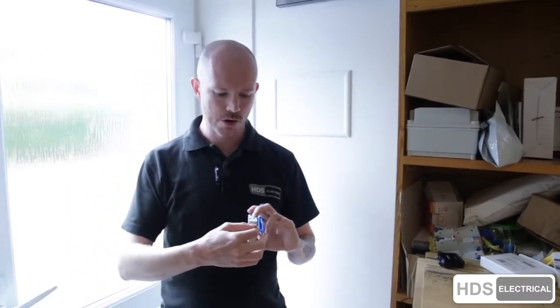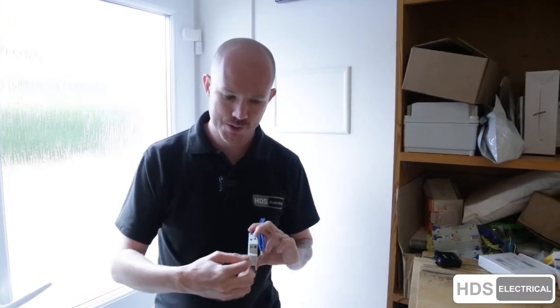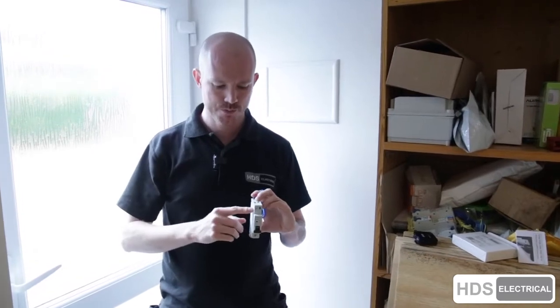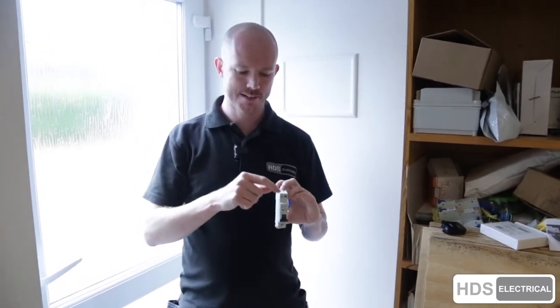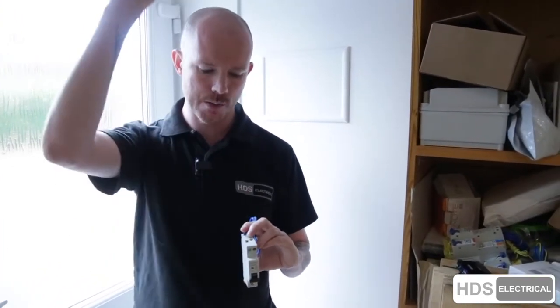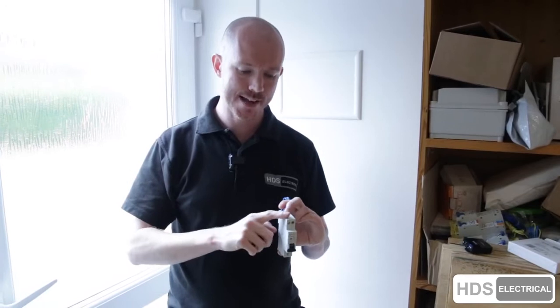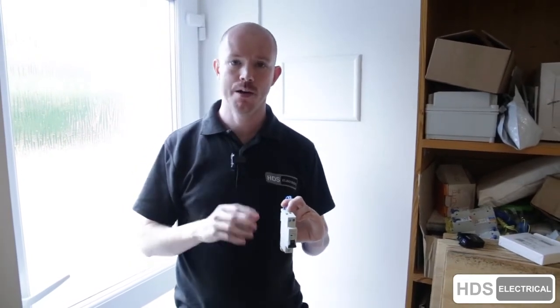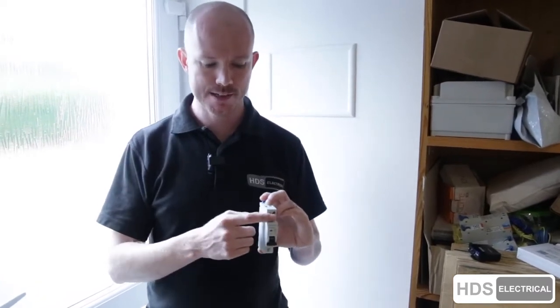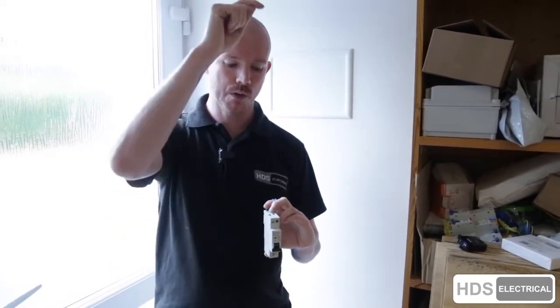That means we've got, say, 100 milliamps coming from the supply, from the live, going through our device, and 100 milliamps back. Ignore the figures, it's just an example. So they're balanced, they're even. The difference you can have is 30 milliamps. So if we've got 100 going out, as soon as we hit 70 back, so we're losing some power somewhere, losing some ampage, this detects the difference between what's going out and what's coming back and trips out.